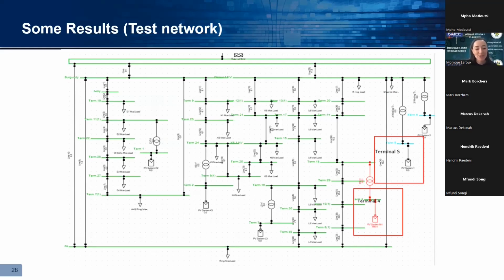I'll just go through this quickly. Okay, so that tool is just for implementation on DIgSILENT. Unfortunately, that can't be done on Excel. And then you would just look at a situation where, for the deterministic one, you would have a single generator connecting to your network. For the stochastic one, you would place generators throughout your network at locations, and then the tools will run and increase the generation in set step sizes, and then the tool will calculate where you're going to see voltage or thermal overload.